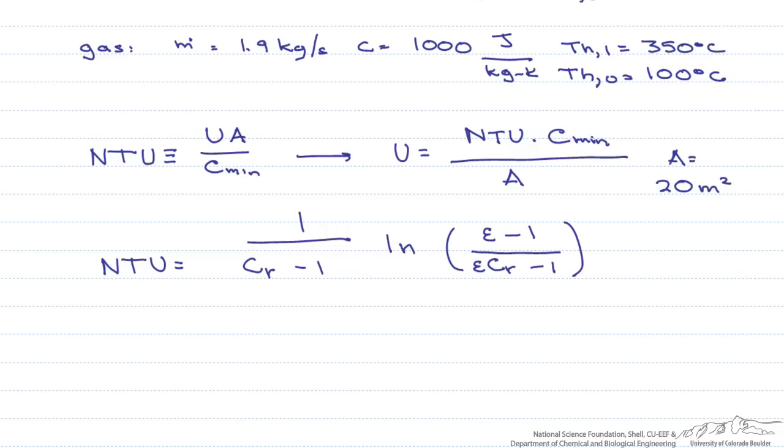The next thing we have to do is define this effectiveness, which is our heat transfer rate over the maximum heat transfer rate. We'll look at the hot fluid. This equals the heat capacity rate of the gases times the temperature coming in minus the temperature coming out, all divided by C min times T H in minus T C in.